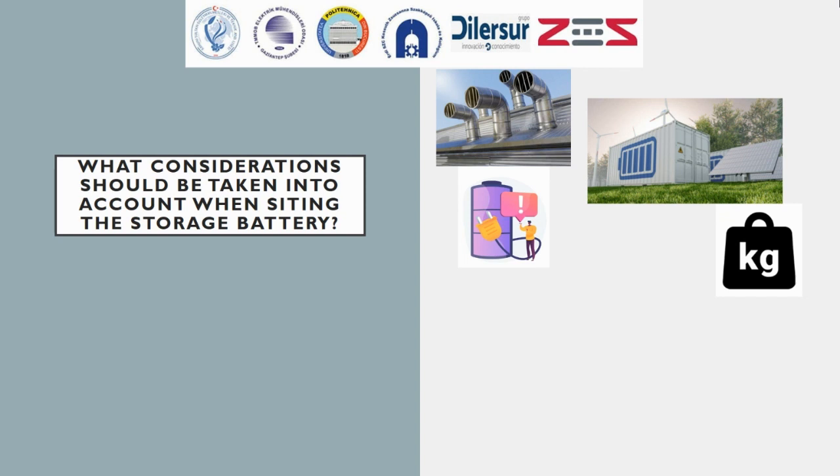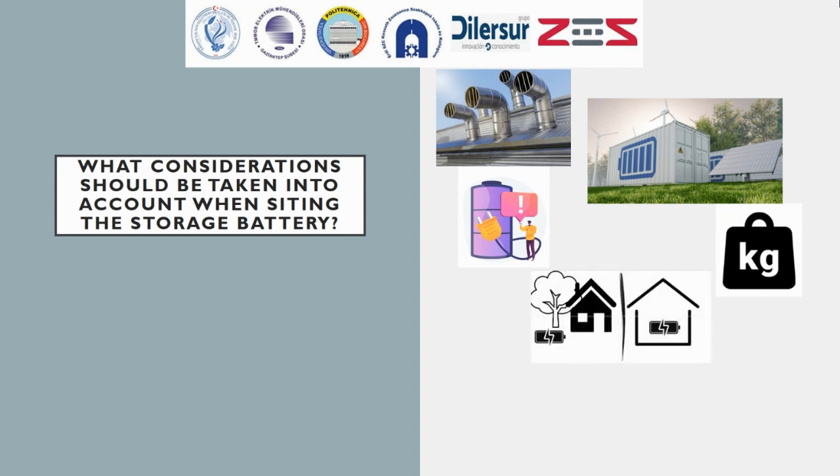5. Weight. The physical size of the batteries, and therefore their weight, up to more than 100 kilograms, will depend on the size of the system and the required lead time. If necessary, the planned room should be checked from a structural point of view. 6. Outdoor or indoor. Enclosed installation is recommended, but accessibility and ventilation are paramount. Avoid areas exposed to direct sunlight or strong heat gain.